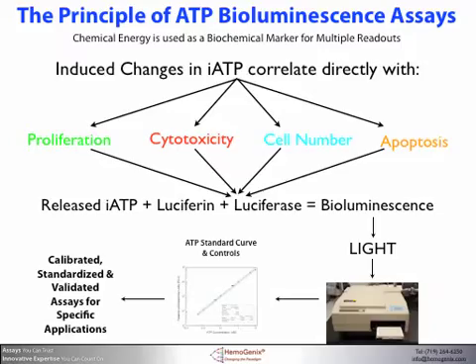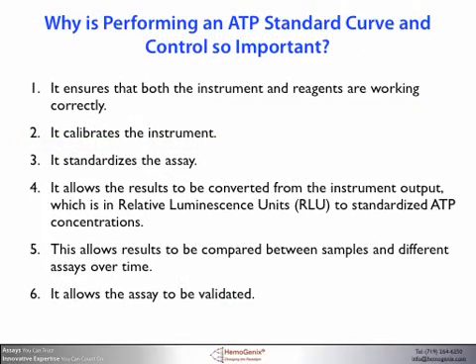There are several reasons for calibration. It ensures that both the instrument and reagents are working correctly. It calibrates the instrument and standardizes the assay. It allows the results to be converted from the instrument output, which is in relative luminescent units (RLUs), to standardized ATP concentrations. This allows results to be compared between samples and different assays over time, and also allows for assay validation. At HemoGenix, we believe that calibrating and standardizing an assay is one of the most important procedures you can perform to ensure that you are getting the best results.